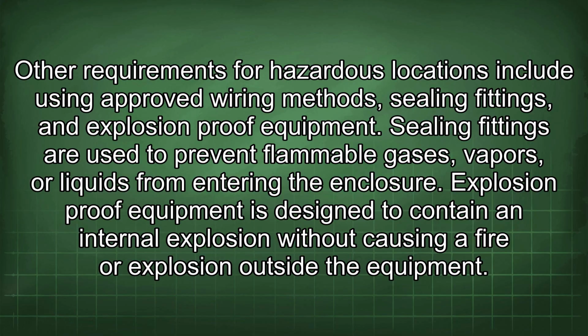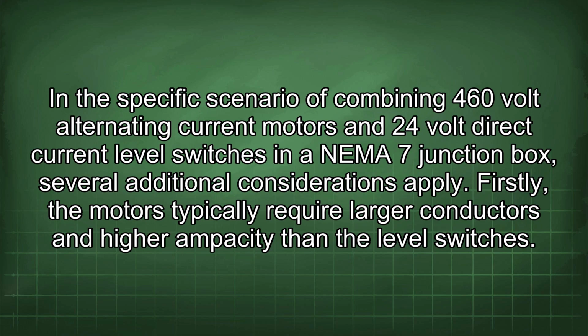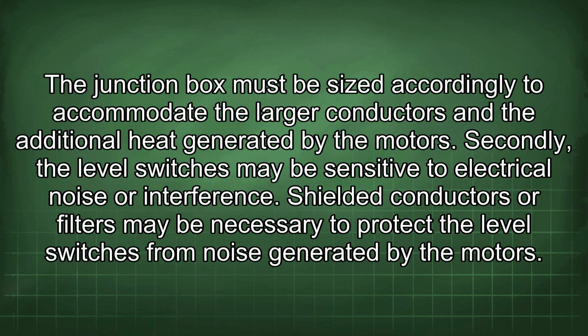Explosion-proof equipment is designed to contain an internal explosion without causing a fire or explosion outside the equipment. In the specific scenario of combining 460-volt alternating current motors and 24-volt direct current level switches in a NEMA 7 junction box, several additional considerations apply. Firstly, the motors typically require larger conductors and higher ampacity than the level switches. The junction box must be sized accordingly to accommodate the larger conductors and the additional heat generated by the motors.